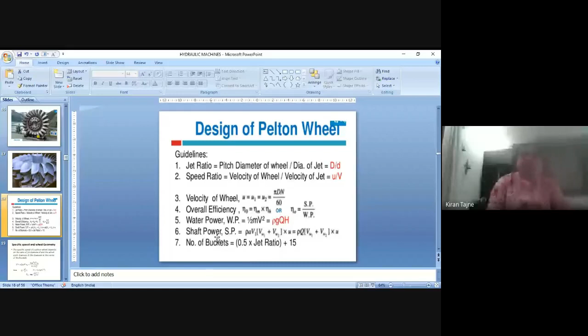Then we can calculate water power, shaft power. Here formulae are given, and the number of buckets you can calculate directly: 0.5 into jet ratio plus 15. 15 is constant. The number of buckets depends on the pitch diameter of the wheel and the diameter of the jet. The ratio of pitch diameter to diameter of jet is known as jet ratio. So this jet ratio multiplied by 0.5 plus 15 is the number of buckets for the runner of the Pelton wheel.